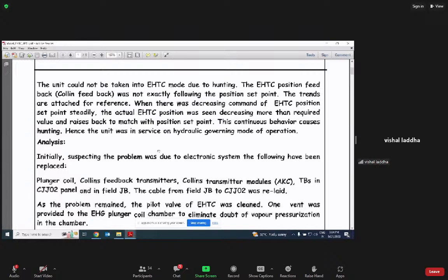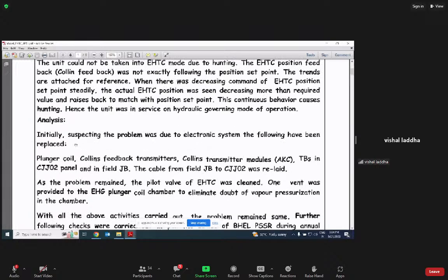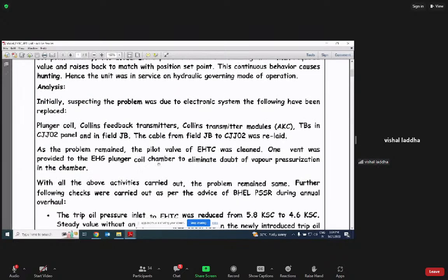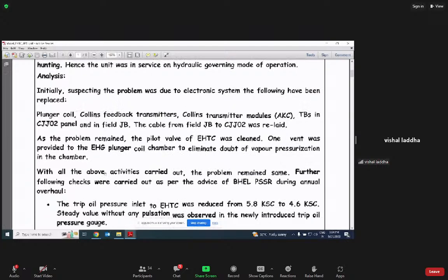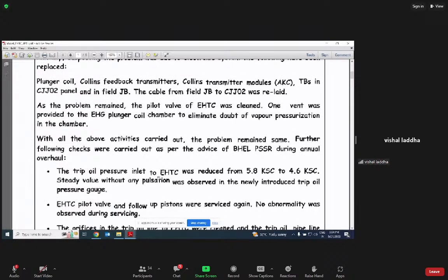The pilot valve of EHTC was also cleaned. A vent was provided to the plunger coil chamber to eliminate doubt of pressurization in the chamber. With all the above activities carried out, the problem remained the same. Further checks were carried out as per the advice of BHEL PSSR during annual overhaul. The trip oil pressure inlet to EHTC was reduced from 5.8 to 4.6 kg. A steady value without any pulsation was observed in the newly introduced trip oil pressure gauge. The EHTC pilot valve and follow-up piston were serviced again, but no abnormality was found.